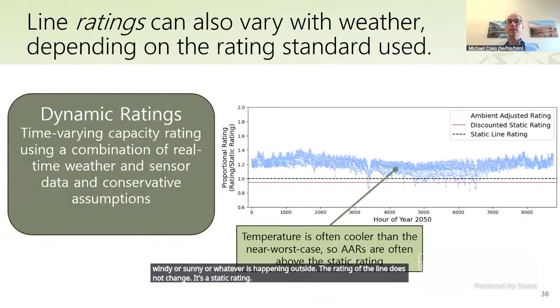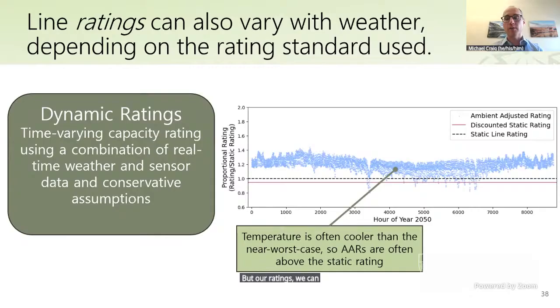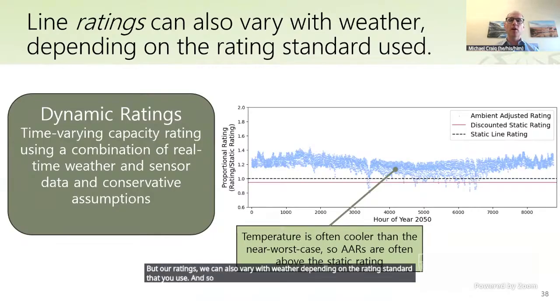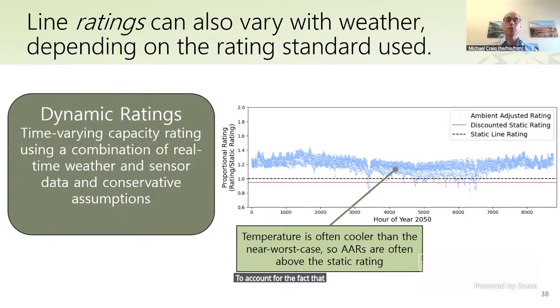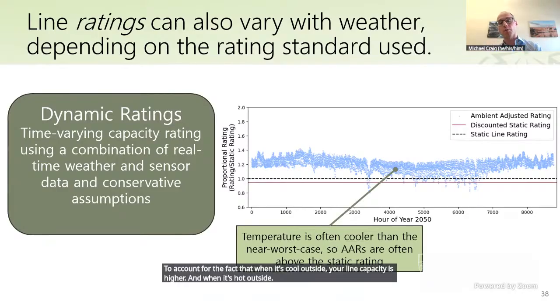But ratings can also vary with weather depending on the rating standard used — these are typically called dynamic ratings. There are several types, but in general they vary the line's rating to reflect that capacity is higher when it's cool outside and lower when it's hot, and that you can move more power through when it's windy, and less when it's not.